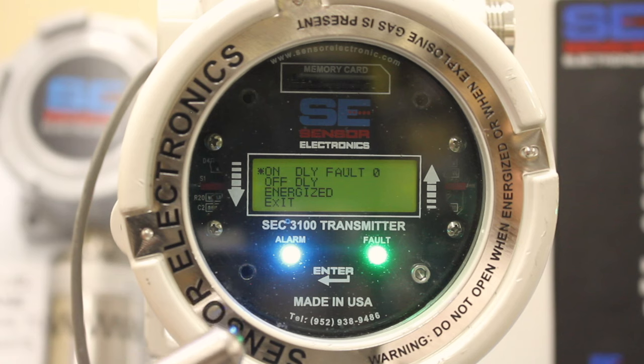And the fault relay is unique because it comes as a normally energized contact. It's the default setting for that, because if you do have a fault, you want to know about it, so that gives you a fail-safe operation of the transmitter, triggering off the fault relay.